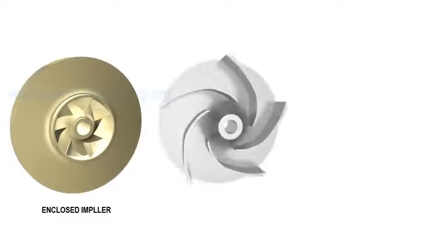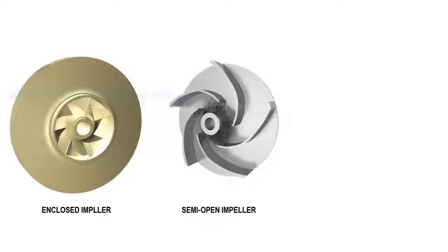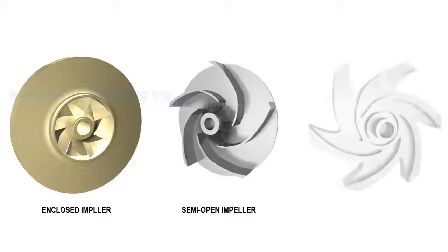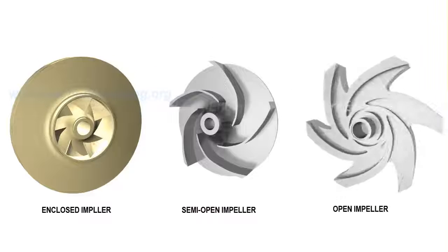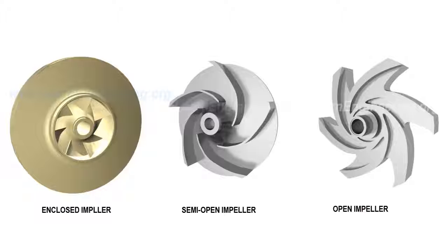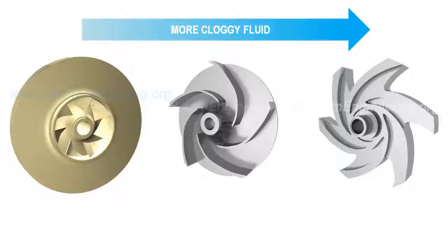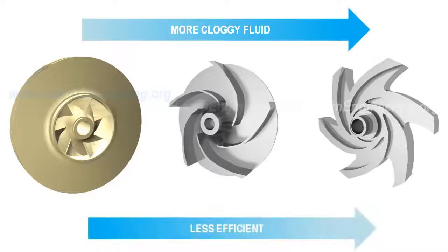Current impeller type is enclosed. Semi-open and open impellers are also in use depending upon application. If the working fluid is cloggy in nature it is preferred to use open kind of impeller, but they are slightly less efficient.